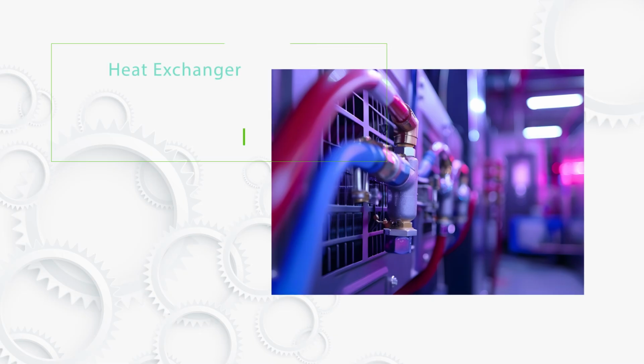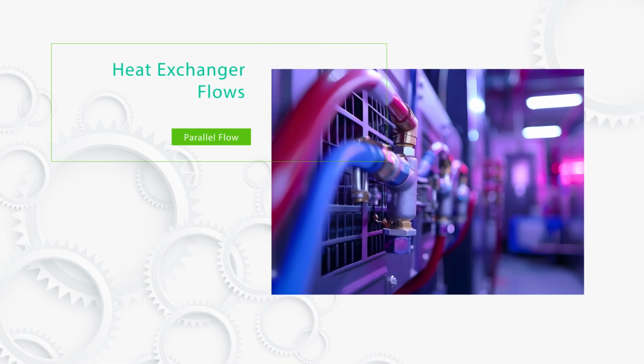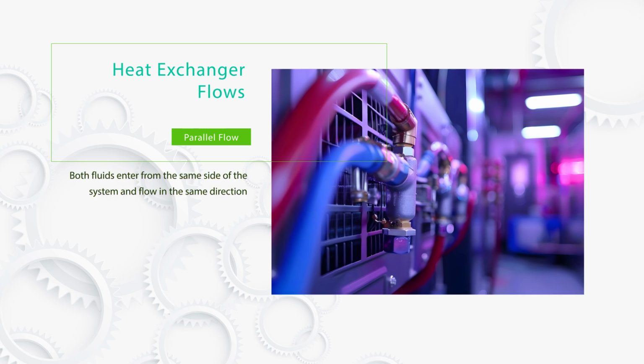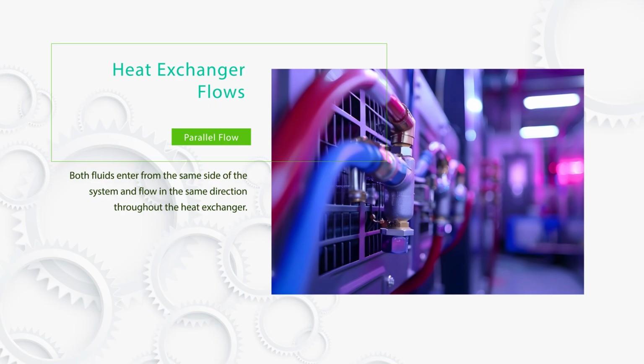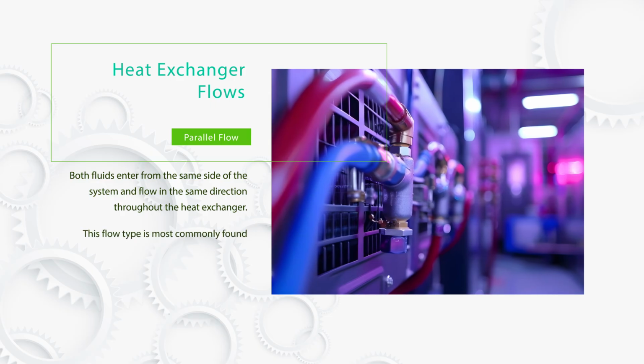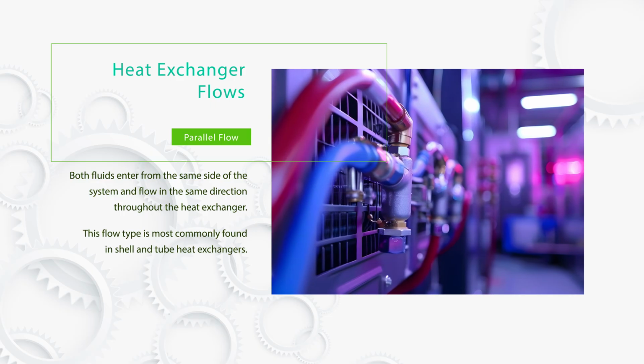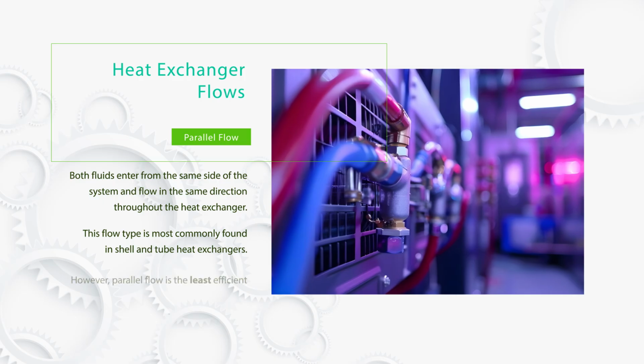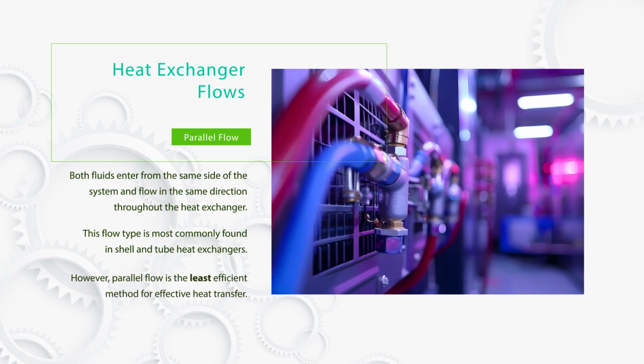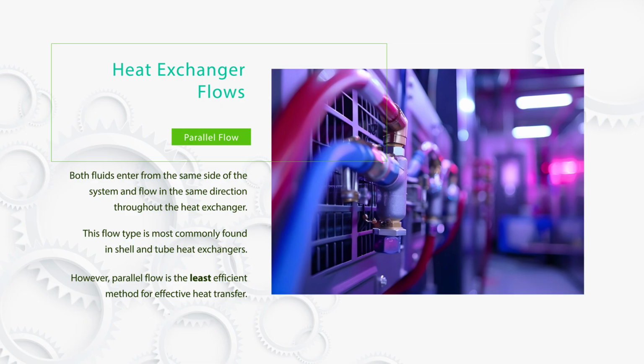Heat exchangers can have three types of flows depending on how they are set up within a process. 1. Parallel flow. Both fluids enter from the same side of the system and flow in the same direction throughout the heat exchanger. This flow type is most commonly found in shell and tube heat exchangers. However, parallel flow is the least efficient method for effective heat transfer.